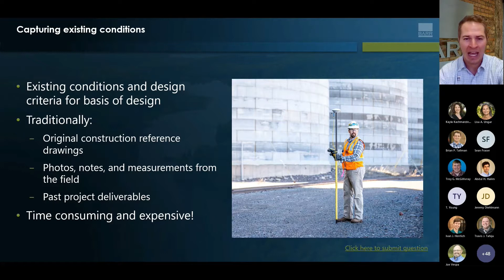So in this step, traditionally, these projects begin with receiving from owners and reviewing many dozens or maybe hundreds of reference files. Those are mainly original plant construction drawings, which are these days generally 30 to 50 or 70 years old. They're very outdated. A lot of remodels that take place over time aren't necessarily documented. Then we also review design deliverables from remodel projects that were executed over time. And then there's an extensive amount of field work to walk down existing systems, take photos, take measurements, and then try to build an accurate picture of the existing condition of the facility. So this process is really time consuming and expensive, both on the engineering end and for the owner. And then it usually results in an incomplete and inaccurate picture of the existing condition of the facility.